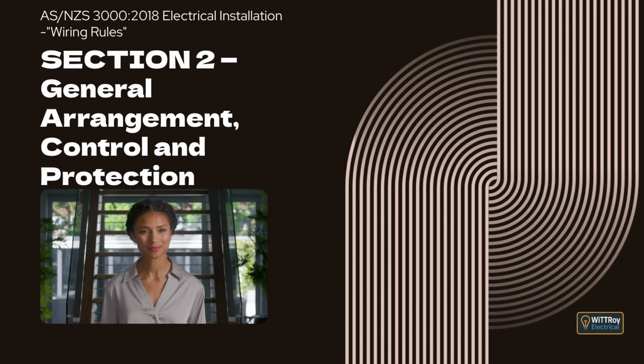Clause 2.7.2, Protection by insulation or separation. This clause is about stopping dangerous voltages from getting into other parts of the installation when two circuits of different voltages sit close to each other. The protection can be achieved by using strong insulation, by screening, or by separating the circuits far enough apart so they can't affect each other. For conductors, we use proper insulation, screening or physical segregation so a fault can't easily jump across.